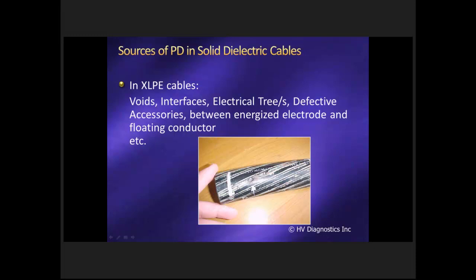That last point is highlighted here where you've got a concentric neutral that's corroded on the outside of the cable. And because you've got that corrosion taking place, you don't get good contact of the ground wires to the outer semiconductor, so you start to get arcing take place. And that arcing can burn holes into the outside semiconductor and finally break down the cable.